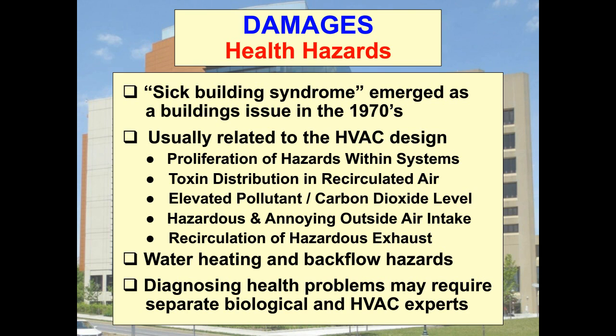Improperly designed outside air intakes can cause serious problems. A design mistake that I've seen repeatedly is placing the outside air intake for a building in a pit below grade. In one building I'm familiar with, every time fertilizer or herbicide is applied to the foliage outside the building, these chemicals permeate the building, causing distress to the occupants.